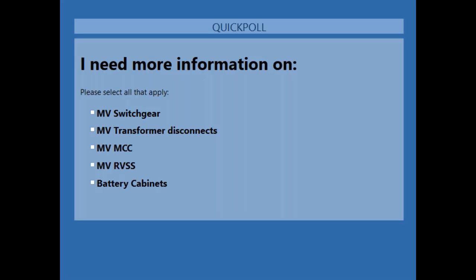So if you're looking at a compact circuit breaker, for example, a Tavrida, the Arc Flash 12 millisecond clearing time circuit breaker in switchgear, that circuit breaker not only has a longer warranty and more mechanical operations than other popular vacuum breakers on the market, and not only does it save space, you could implement it in one of those 26-inch wide sections that Michael indicated, but it's half the size and a third the weight of a conventional medium voltage breaker. So regardless of how big or how little you are physically, working with a conventional breaker, you need a crane, whereas with one of these compact breakers, an individual can easily remove and transport it around.